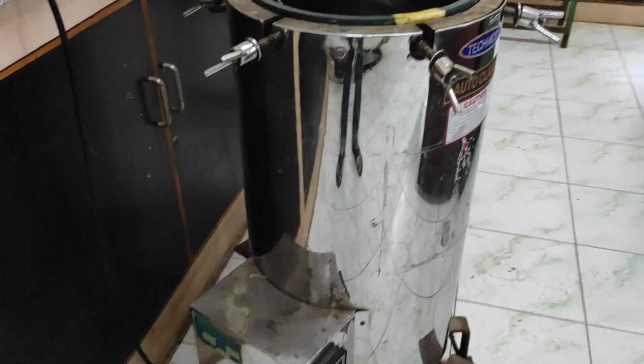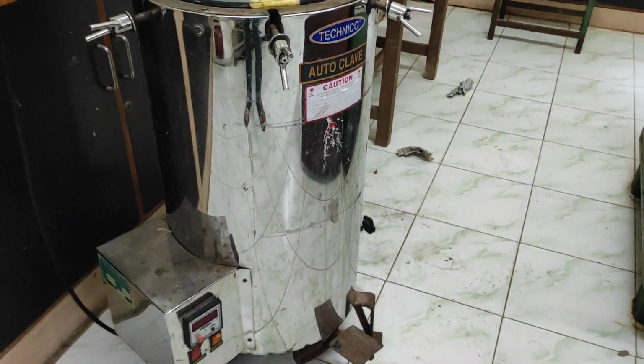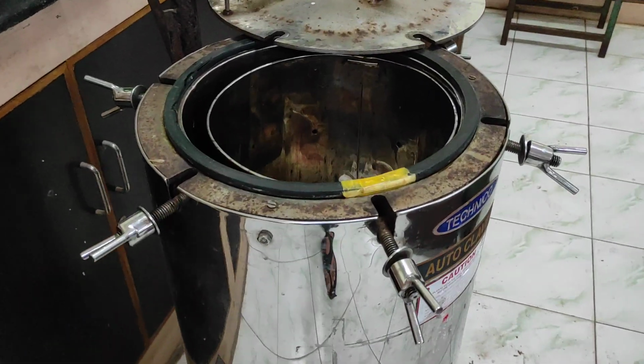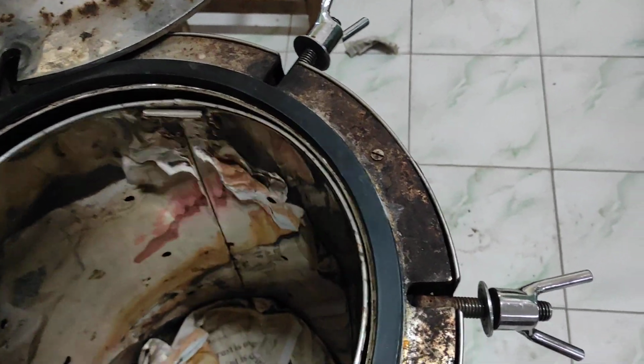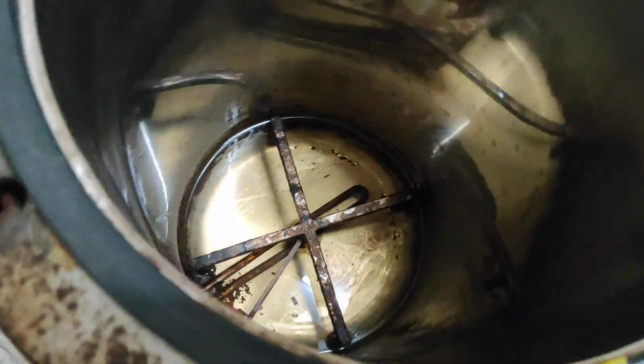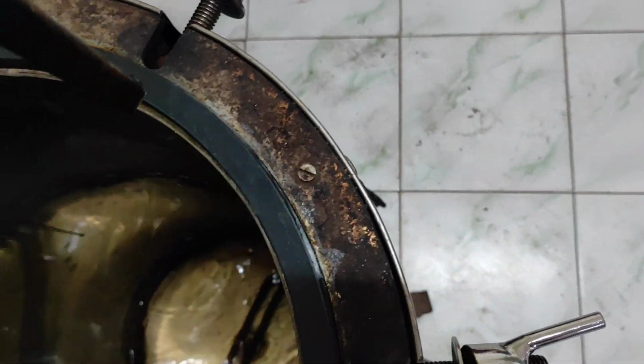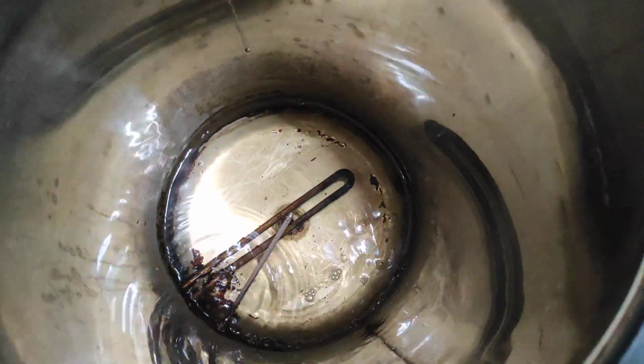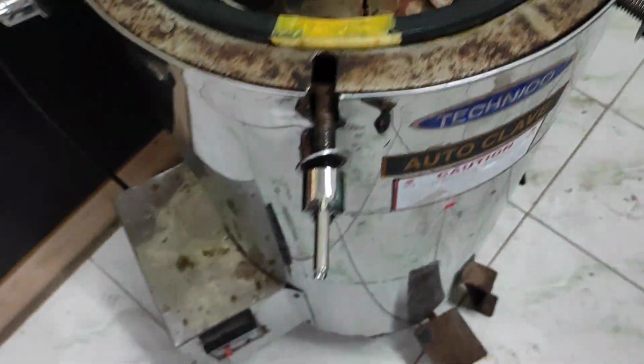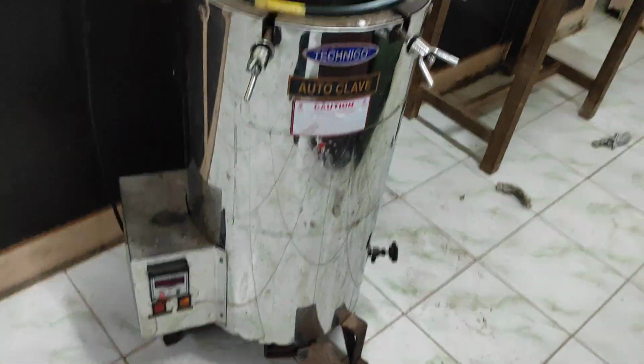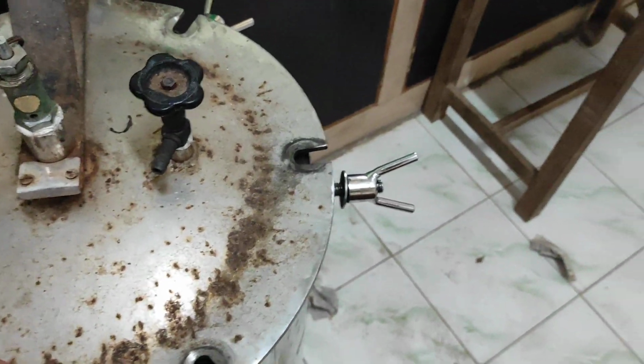This is a small vertical autoclave which can accommodate 1 to 2 liters of medium. If the requirement is a smaller amount of medium, we use this autoclave. This is very old, I think more than 10 years old, but still it is in working condition. You can see here the heating element and water, nothing more than that. One sensor is also there which senses the temperature inside. And this is the container in which we keep the medium. We have to use it manually. This is the pedal, and this is the lid. We have to operate it this way.